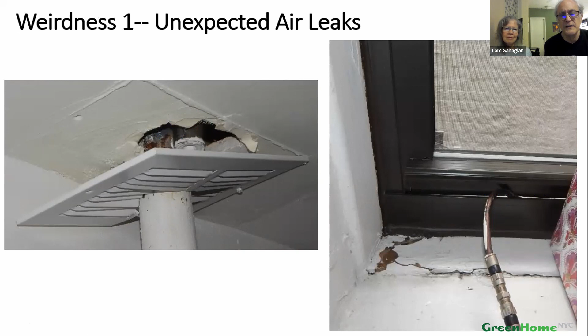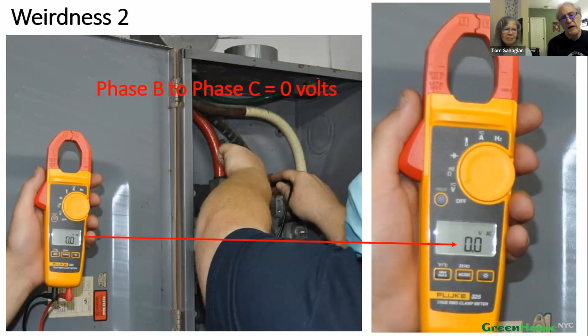This was completely insane. We found out that on the top floor, the voltage difference between phase B and phase C was 0, and it was supposed to be 208. We were really scratching our heads on this.